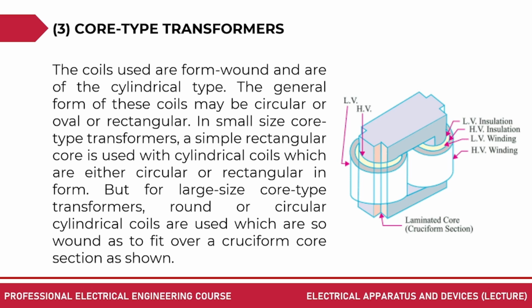The coils used are form wound and are of the cylindrical type. The general form of these coils may be circular, oval or rectangular. In small size core type transformers, a simple rectangular core is used with cylindrical coils, which are either circular or rectangular in form. But for large size core type transformers, round or circular cylindrical coils are used, which are so wound as to fit over a cruciform core section as shown.